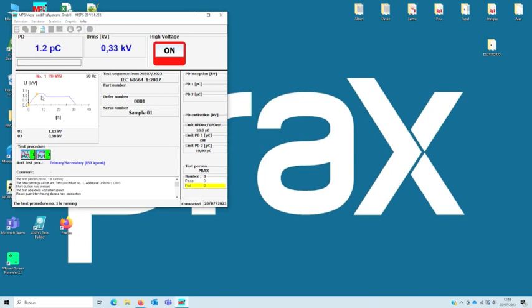So here we're increasing the voltage up to 1.875 times the working voltage, which is 1.13 kilovolts. Here we can see that we are using RMS for a sinusoidal waveform. This is the reason why we are making this conversion. Then we reduce the voltage to 1.5 times the working voltage, the 900 volts. Here we wait 10 seconds to ensure that the partial discharge is stabilized. And then in these last 5 seconds, we are making the measurements of the partial discharge.